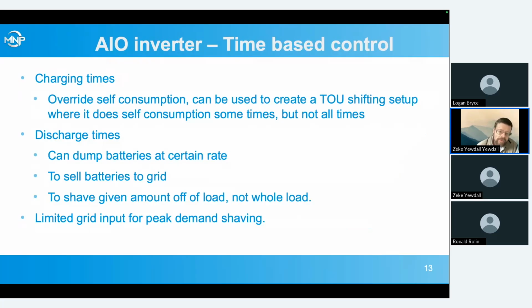Time-based control. This is usually what we use when we are trying to do time of use setups where we have peak demand times or peak rates during certain times of the day. So we want to change what the inverter does at different times of the day.